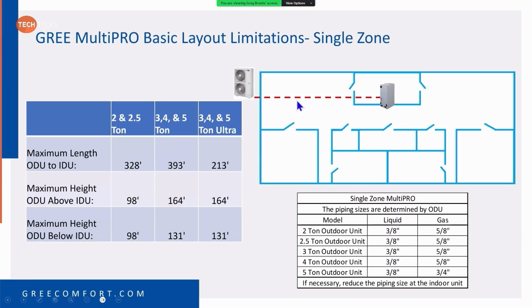Then we follow the rules in place. Remember, this is always going to be 10 feet minimum, and that is sized by the outdoor unit. So that's easy to remember. Remember your maximum lengths, outdoor unit to indoor unit. Maximum height, outdoor unit above indoor unit, and maximum height, outdoor unit below indoor unit. Your pipe sizes, again, are, like I said, sized by the outdoor unit. The only one that's going to be 3/8, 3/4 is the 5 ton. The rest of them are going to be 3/8, 5/8.